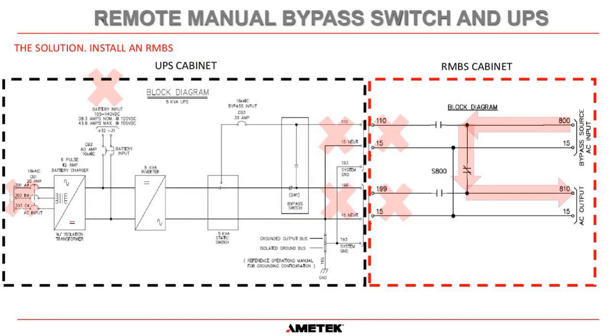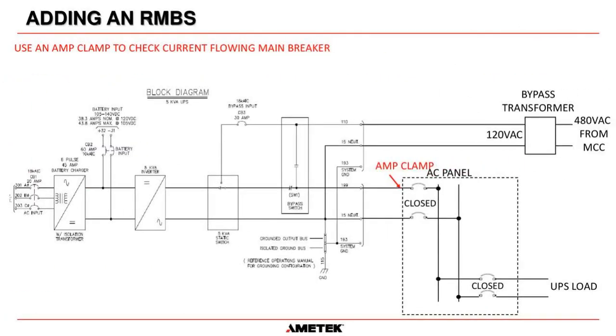But everybody says, well, I don't have an RMBS and I have a UPS with an internal bypass switch. How do I install an RMBS cabinet without taking an outage on my critical loads? And there is a way that you can do that. And that's what the next slides are going to be, is how do we install an RMBS into a system that only has an internal maintenance bypass switch while the UPS critical loads are still live. In other words, you're in a situation where you have to install an RMBS, but you can't take an outage on your critical loads. Okay, so this drawing here shows you exactly what that system would look like.